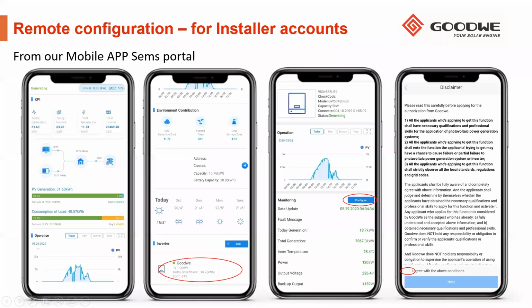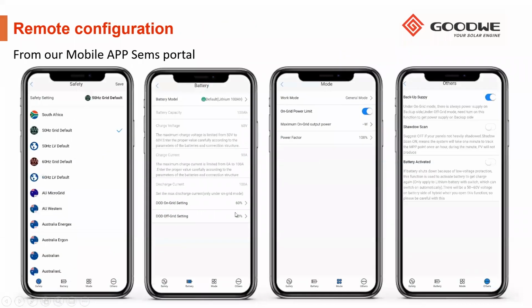Thereafter, you'll see all these menus. These are just about all of the settings. There are a few advanced settings that aren't available here, but just about all of them are here. You'll see we have the country code settings, the battery settings. Especially for customers that want to adjust the on-grid depth of discharge to reserve more battery power, or change the work mode to backup when we have a lot of load shedding to make sure the battery is 100% full, you can do this remotely and there's no need to go to site to do it.